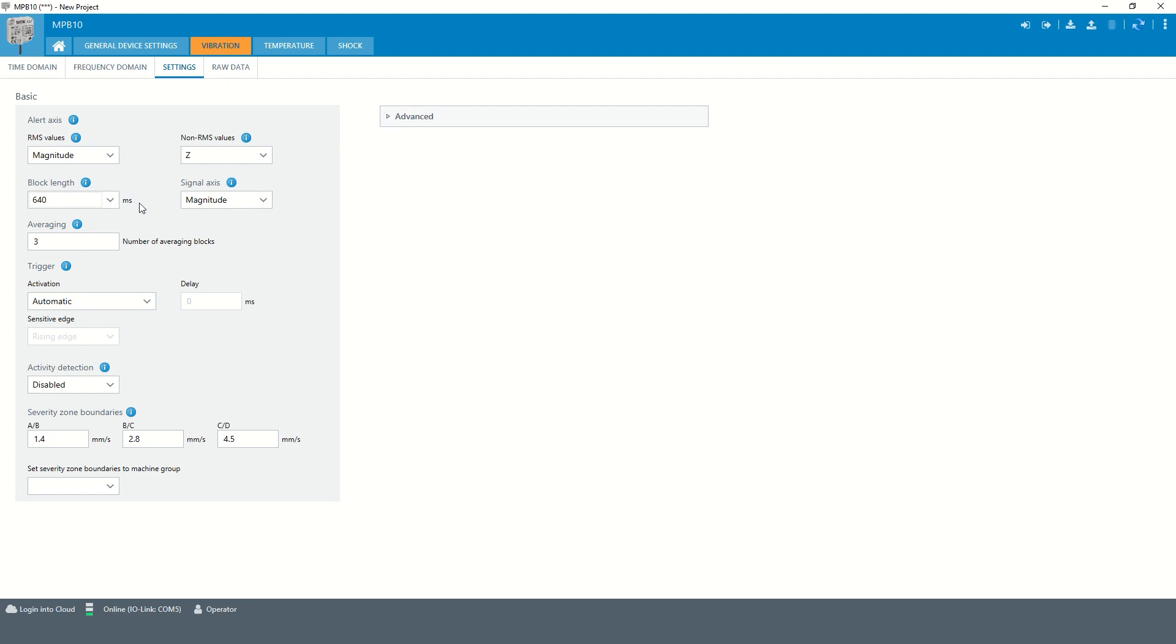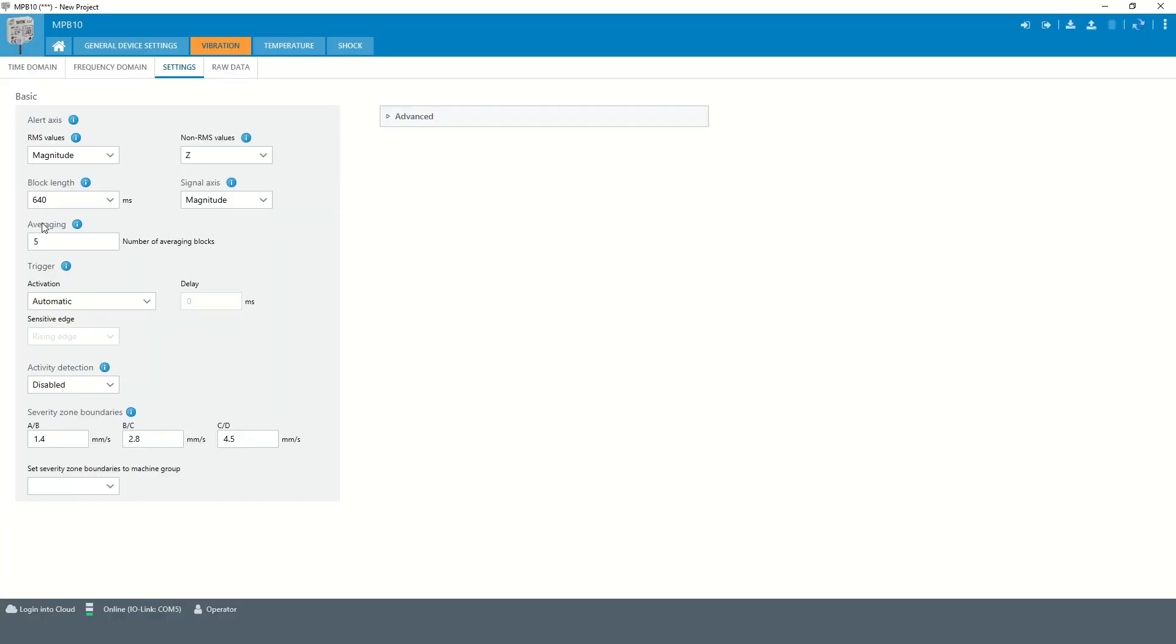A shorter block length means more frequent updating. A longer block length means higher averaging and thus lower noise of the indication values. By averaging over several blocks, the number of blocks can be adjusted here in the settings, the noise of the indication values can be reduced even further. However, this reduces the update rate of the vibration key values.